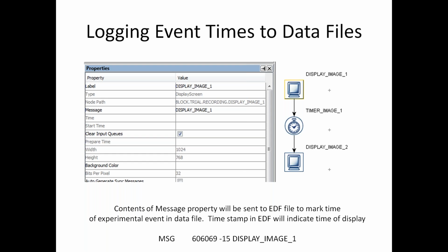Okay, and the messages are super fast. There are lots of different ways to test it. A very simple way is to make an Experiment Builder project and just send back-to-back messages, or make a Psych Toolbox from MATLAB example and just send back-to-back messages. Messages take way less than a millisecond to be sent from the display PC to the host PC. So basically, if you need 1 millisecond timing precision from Experiment Builder, then the message timing is almost negligible, right? So it's sub-millisecond.